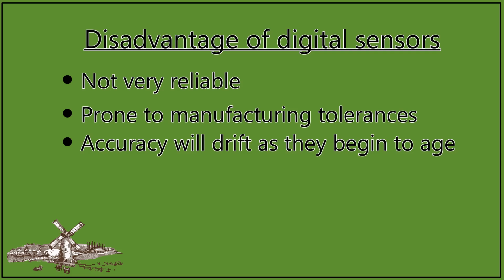Now, the reason why our sensors are so inaccurate is because when they manufacture them, they cannot manufacture them perfectly. So some sensors will be a bit longer, some a bit shorter, some a bit thicker, some a bit thinner. And so we would have to take these differences into account when we analyze the message coming back in order to get the correct temperature. Now, that wouldn't be terribly difficult to do because they would be able to account for that at the factory. But to make our lives a little bit more difficult, the age of the sensor also plays a very crucial role in the temperature measurement or the humidity measurement that it gives you.